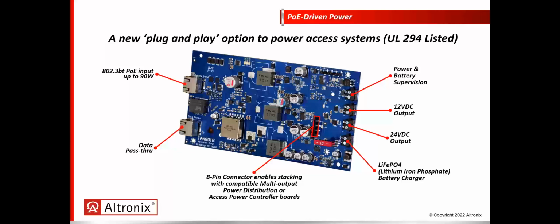On the left-hand side, you have your PoE input and your data pass-through output. We know you're going to have another device, whether it's an access control board, a security burglar alarm board, or another network device inside that enclosure. So instead of running 2 home runs of Cat 6 cable, one for the data to the access controller and another for the PoE to power the Tango board, we can pass that right through with a single cable, connect to the access control board, and pass the data through, leaving just a single cable deployment.